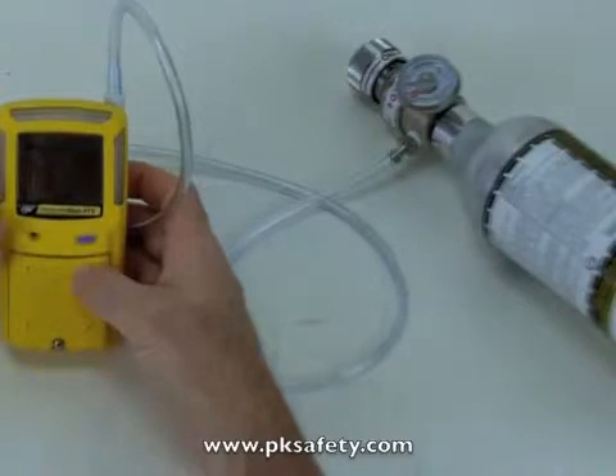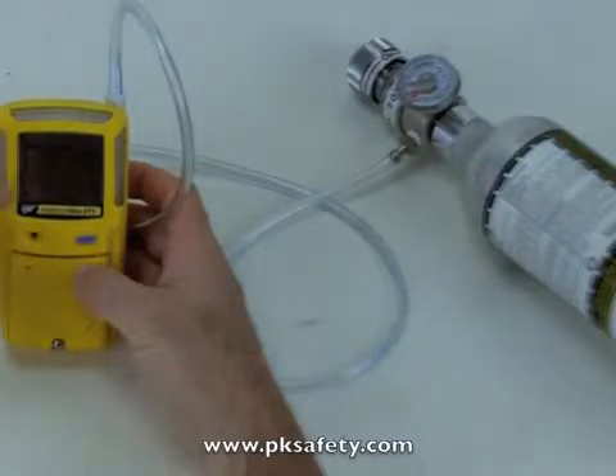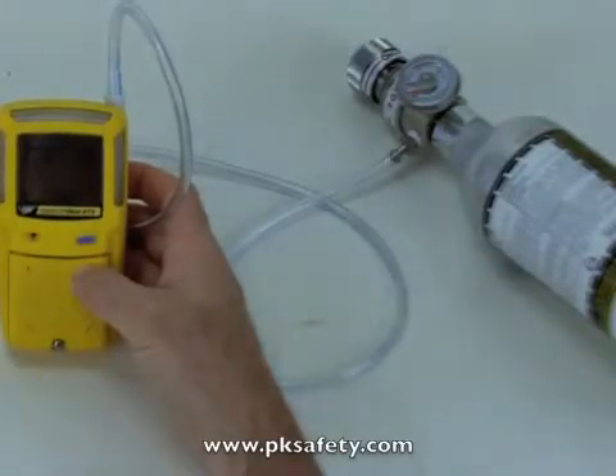Now, this is going to take about 2 minutes as it goes through its cycle here. This regulator flows a ½ liter per minute, so we're going to use about 1 liter of gas. The cylinder here, which is the one that comes in their kit, contains 34 liters. You should get about 30 calibrations out of that cylinder. So we'll just let this run and come back to it.